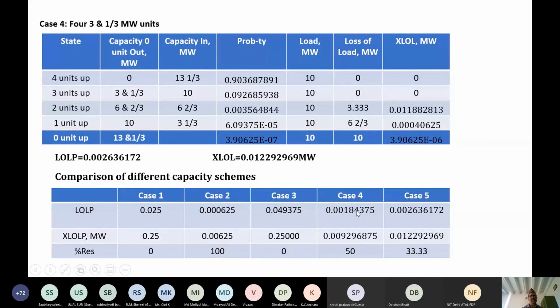In case 4, reserve margin is 50%. So loss of load probability is higher than in case 2, because in case 2 we had 100% reserve margin. Case 4 we have 50% reserve margin. And similarly, the expected loss of load is also higher here compared to case 2. And in case 5 now, the reserve margin has been further reduced to 33.33%. Loss of load probability is higher than in case 4, and expected loss of load is also higher than in case 4. Okay, so the higher the reserve margin, the lesser will be the loss of load probability and expected loss of load.